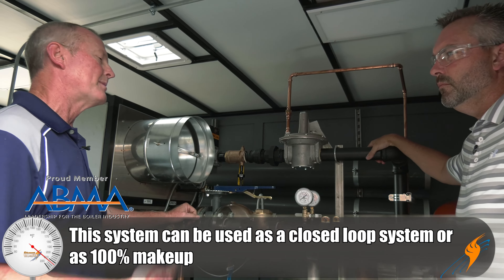Now, let's talk about what we were actually in — a hot water rental boiler. We've got quite a few units coming to our customers. These are 2 million BTU units, but what if you needed 4 million? We've set these up with configurations where we can tie 2 or 3 of them together. If you have a 4 million BTU load, we tie them into a manifold we've built up. Six million — same thing. Very seldom do you ever get more than 6 million on a system like this. We set them up so you can stack them and deliver as much hot water as needed.